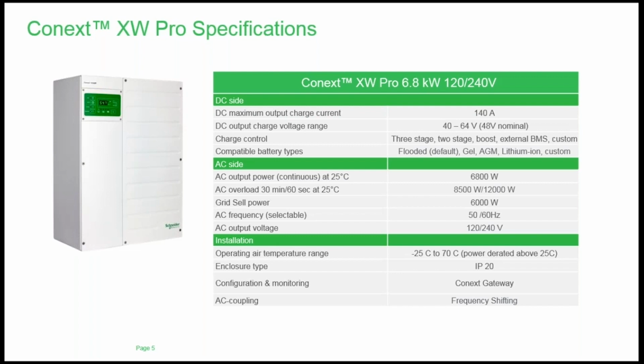Grid sell power is 6 kW. Frequency selectable, it is a split phase system, 120/240. It has a very wide temperature range, -25C to 70C. AC coupling is another feature that's built into the XW Pro, and we provide frequency shift regulation.